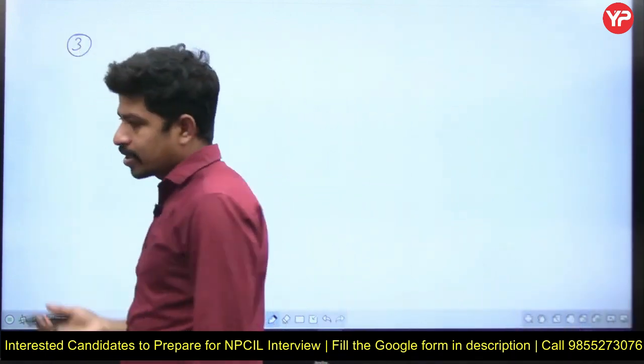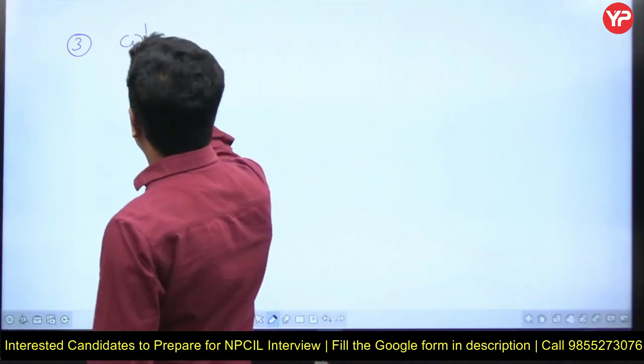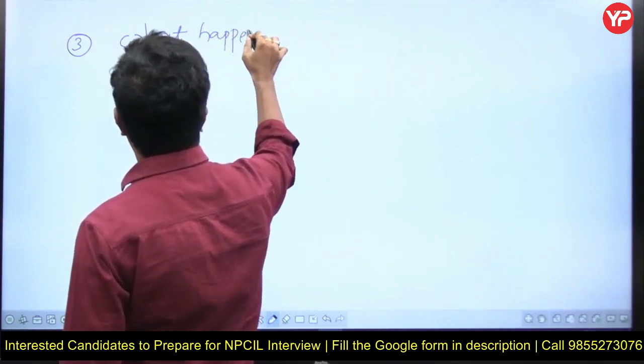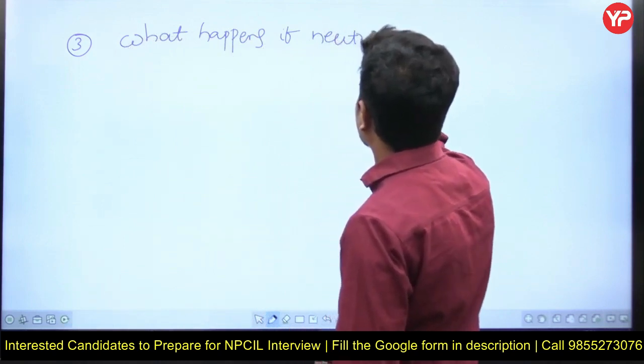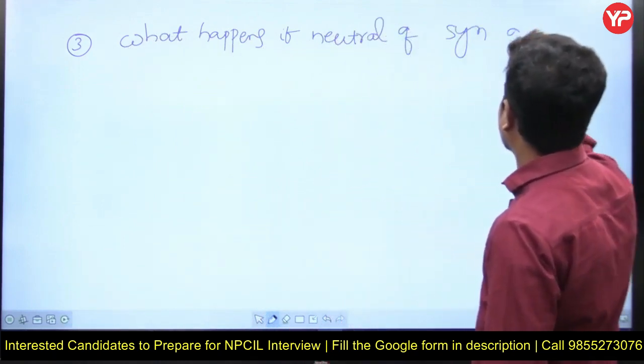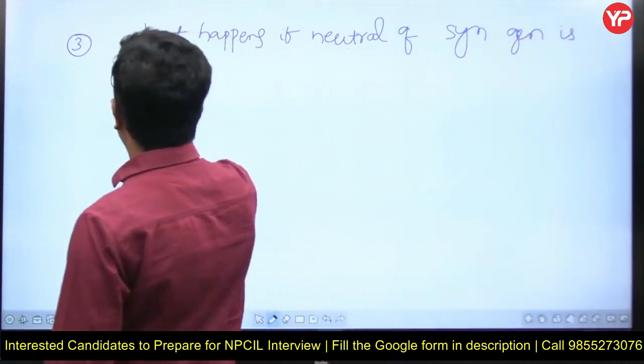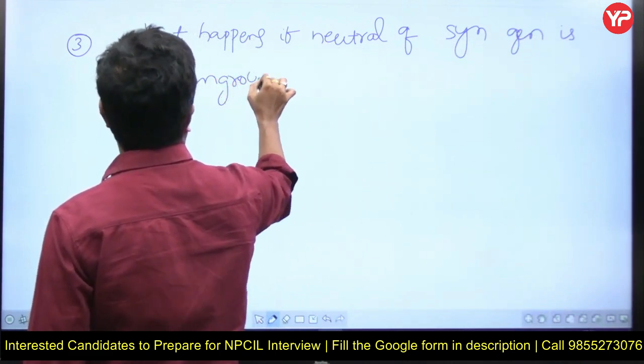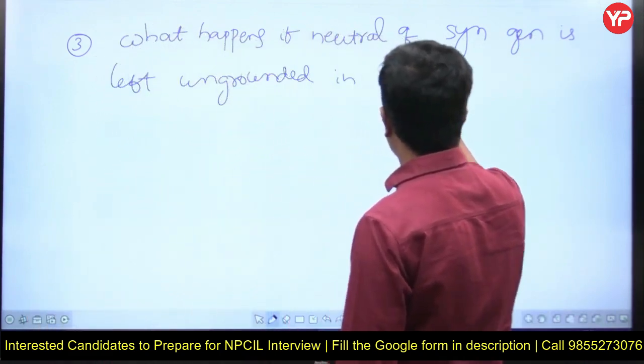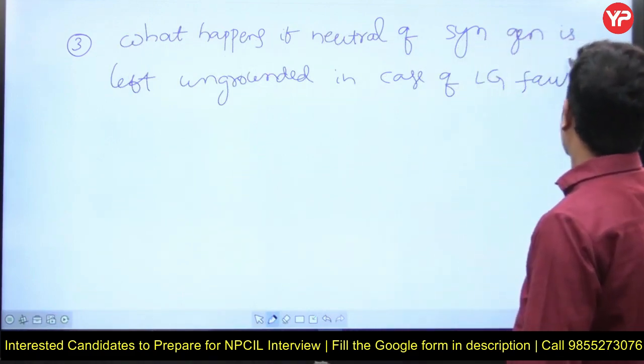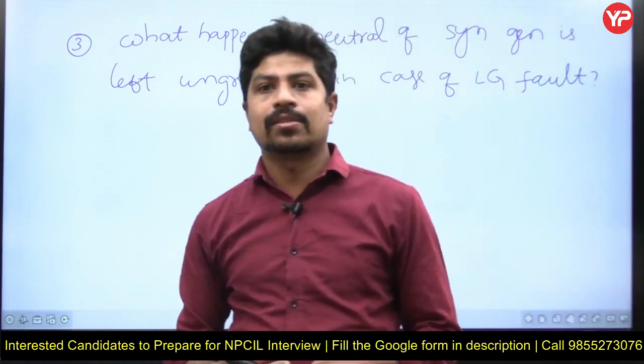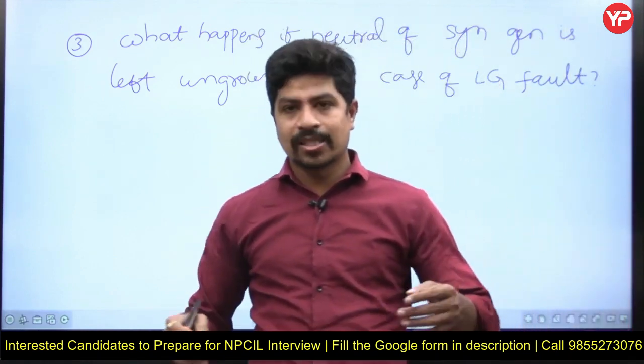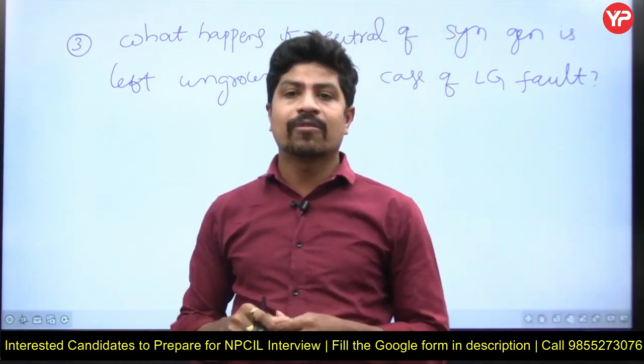The next question that can be framed here: the discussion happened between LG and triple L faults. Now he will ask you, what happens if the neutral of the synchronous generator is left ungrounded in case of an LG fault? Most of you study standard examples, an LG fault with the neutral grounded by default. What happens if the neutral is left ungrounded?